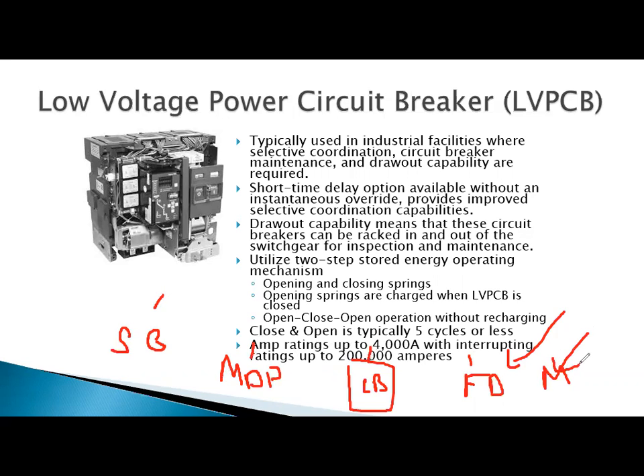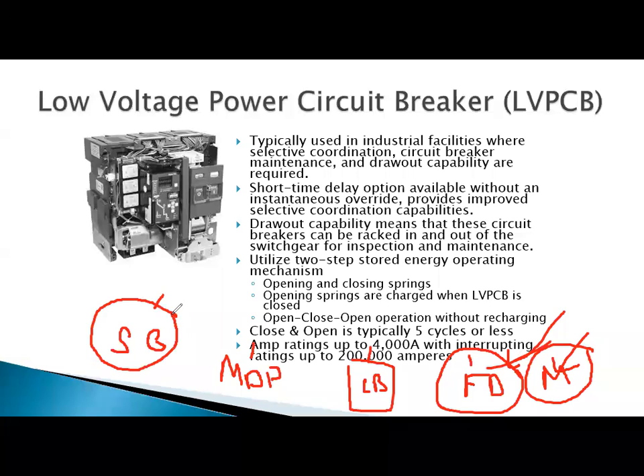What does selective coordination mean? It means that the overcurrent device that is the closest to the equipment, so this fused disconnect, should have the quicker clearing time. And the quicker clearing time is going to clear just the motor. That's the only place we have the problem. Let's get rid of our problem with the first overcurrent device. Can you imagine if we used the switchgear to clear this problem? Because if we did, we just lost power in our whole facility. So really not a good idea.